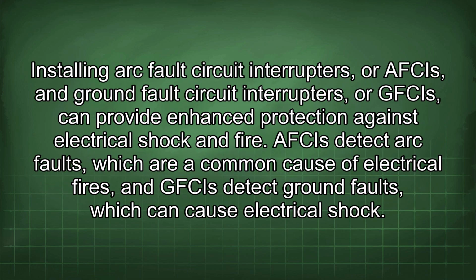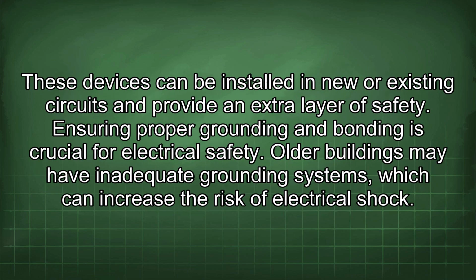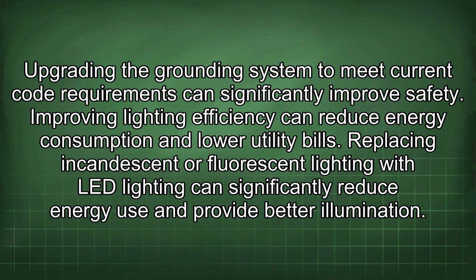Installing arc fault circuit interrupters, or AFCIs, and ground fault circuit interrupters, or GFCIs, can provide enhanced protection against electrical shock and fire. AFCIs detect arc faults, which are a common cause of electrical fires, and GFCIs detect ground faults, which can cause electrical shock. These devices can be installed in new or existing circuits and provide an extra layer of safety. Ensuring proper grounding and bonding is crucial for electrical safety. Older buildings may have inadequate grounding systems, which can increase the risk of electrical shock. Upgrading the grounding system to meet current code requirements can significantly improve safety.